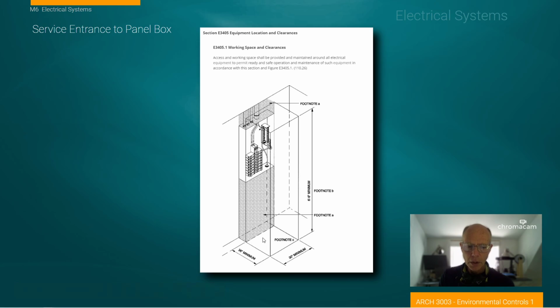The idea of giving this space is to protect anyone working on this panel box from falling into the panel if they have a short circuit while working on it, or if they're grounded and accidentally touch a live wire and are rendered unconscious. You don't want them falling into the panel—you want them to have clear room to fall away or get away from the electrical hazard.